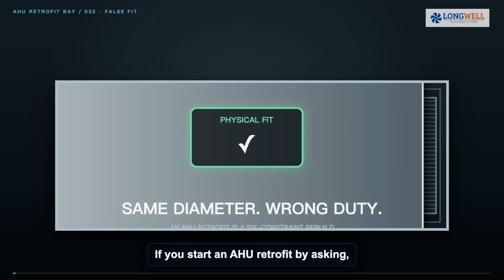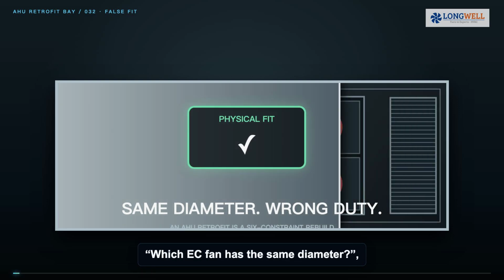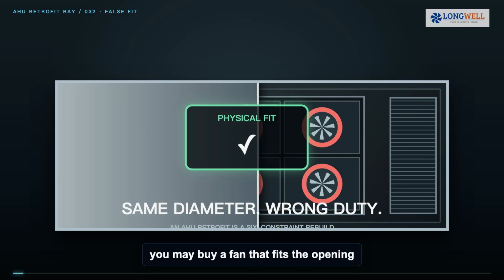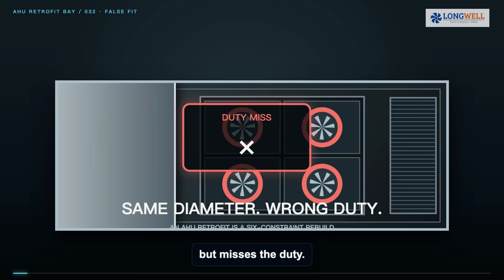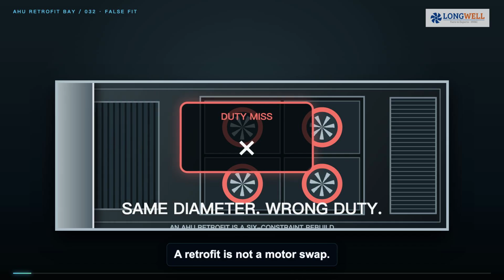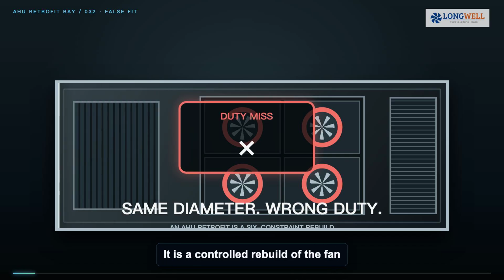If you start an AHU retrofit by asking, which EC fan has the same diameter, you may buy a fan that fits the opening but misses the duty. A retrofit is not a motor swap. It is a controlled rebuild of the fan section, with 6 constraints that must agree.